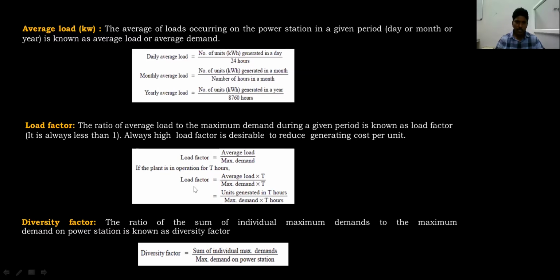The same thing, load factor, we can write in a different form: average load into time divided by maximum demand into time. Daily average load into time gives you the number of units generated in a day, divided by maximum demand into T hours. Sometimes in problems they may ask for load factor directly, so if the information is given as units generated in T hours, then you can directly substitute and do the problem.